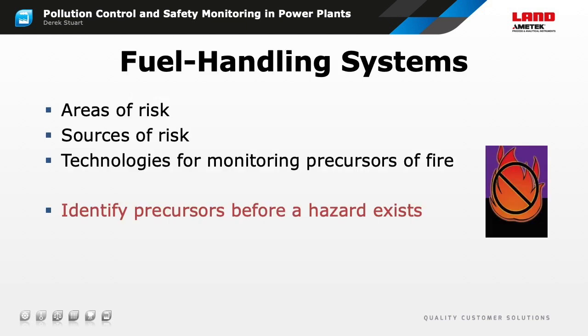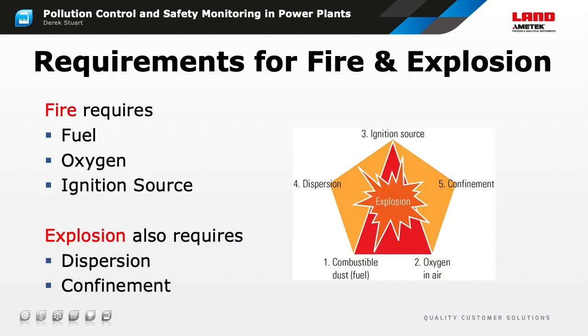I'm going to discuss the areas of risk in fuel handling systems and the technologies available to detect spontaneous heating and spontaneous combustion. Our aim is always to identify the precursors so that the site operation can make the fuel safe before a fire occurs. Of critical importance is the problem of oxidation. When coal or biomass particles are exposed to air, the volatile components combine with oxygen in an exothermic reaction, leading to spontaneous heating. Since this part of my presentation concerns fire and explosions, let's review some basic theory.